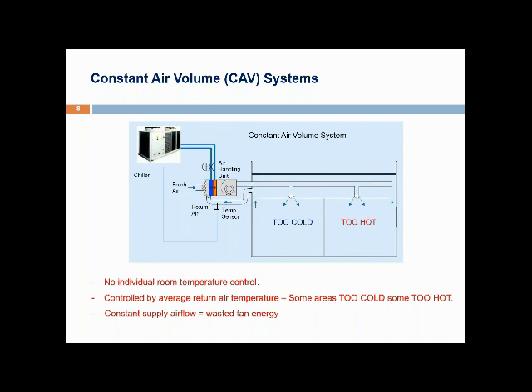The constant air volume system varies the cooling supply by varying the supply air temperature, but it cannot provide different temperatures for different rooms. The room with the temperature sensor gets overall control, or alternatively everyone has to live with control based on the average return temperature — meaning some rooms will be too hot and some too cold. And by having constant airflow whether cooling is needed or not, it wastes fan energy.